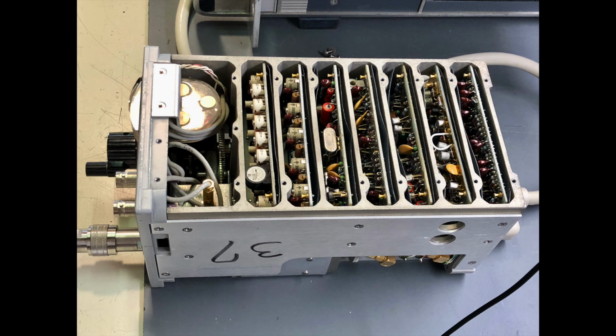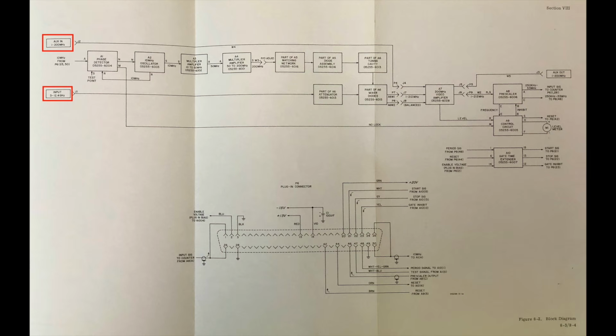So I started the troubleshooting with the block diagram. There are 2 inputs, the main RF signal to be measured and the prescaler input. I noticed that the prescaler input only worked above about 100 MHz, so that needed to be repaired first. If the prescaler doesn't work, then the main RF input can't be measured either, because the heterodyne converter is mixing the input signal with a harmonic of 200 MHz. The mixer output will be something between 1 and 200 MHz, which the prescaler must divide by 4, so it remains in the measurement range of the 5245L.